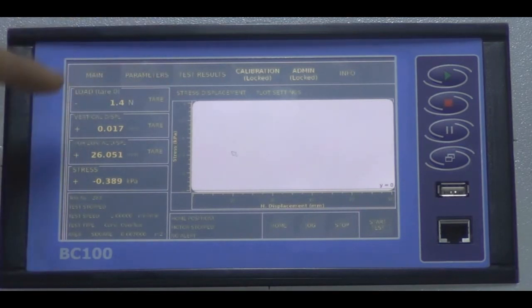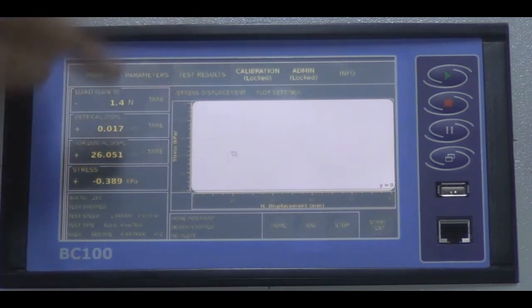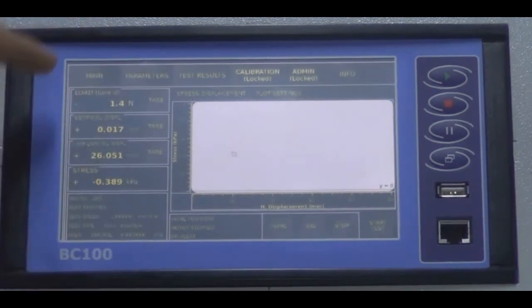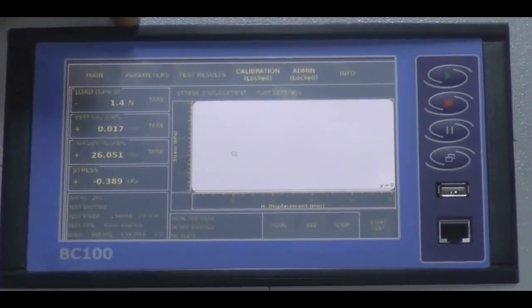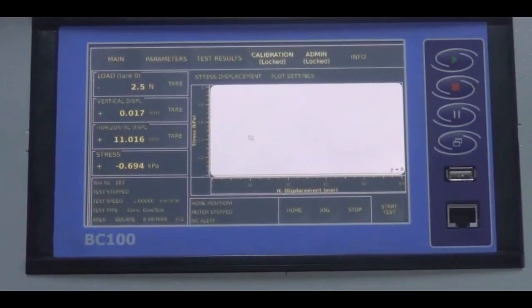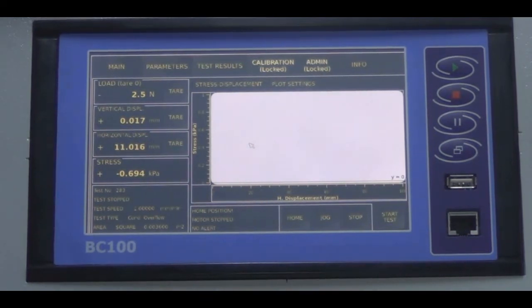In the load, vertical, and horizontal displacement values, there are tare buttons. Before starting the test, after everything is assembled, you should tare all the values to start from zero. In the load segment, you will observe the tared load in parentheses. The second group of buttons in the bottom right corner are: home, jog, stop, and start test buttons.